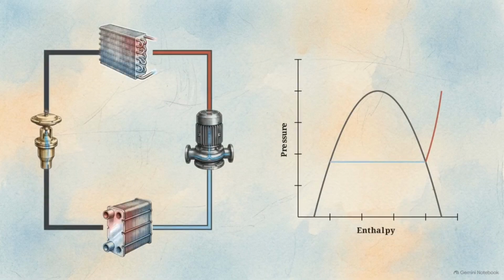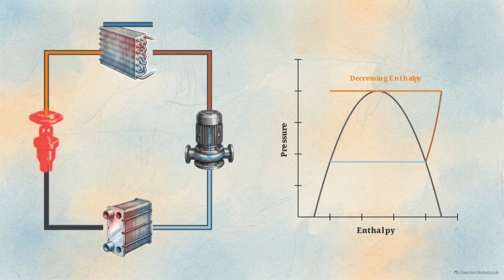Here, the system executes the actual heat rejection. Hotter than the surrounding environment, the refrigerant sheds its accumulated thermal energy to an external medium, condensing back into a liquid. On the chart, enthalpy decreases while pressure remains constant and high. Finally, this high-pressure liquid reaches the fourth node, the expansion valve. The valve acts as a strict bottleneck, forcing a sudden, dramatic drop in pressure. This causes the temperature to plummet, priming the refrigerant to re-enter the evaporator and absorb more heat. We track this final phase as a steep vertical drop in pressure on the chart, closing the loop entirely.